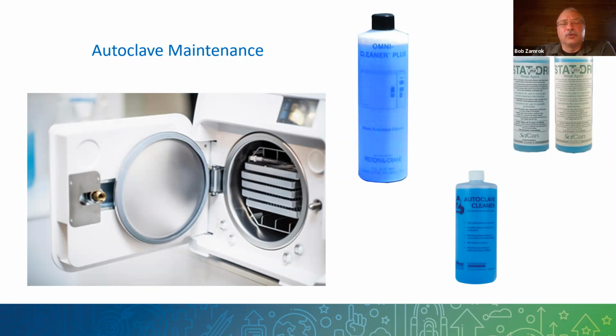When running your autoclaves, especially during cleanings, inspect all the gaskets, your door gaskets and everything. Most manufacturers - your Tuttnauers, your Midmarks - their gaskets are interchangeable, so you can reverse the gasket and get an extended life out of it. Maybe once a month or every 6 months, reverse the gasket - you'll get a longer life and avoid steam leaks.